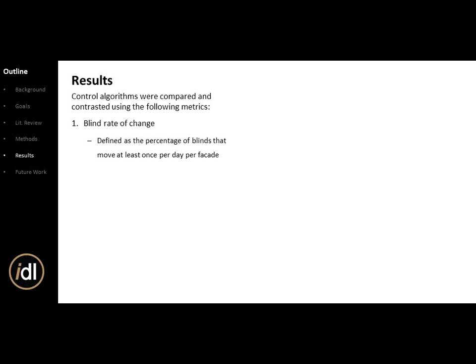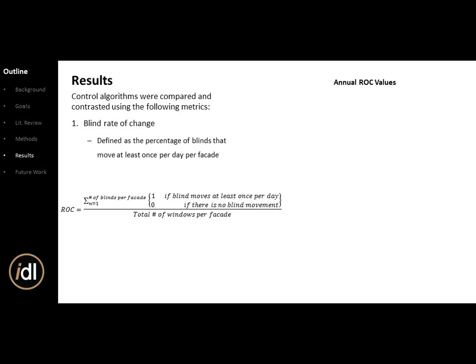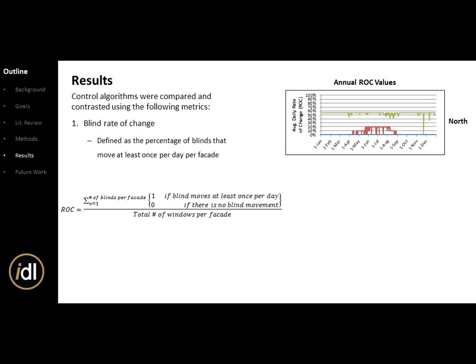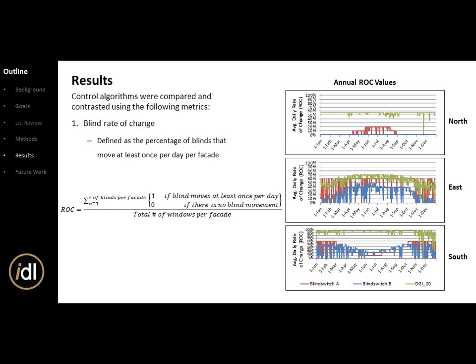The results I'll cover include blind rate of change, defined as the percentage of blinds that move at least once per day per facade. Annual rate of change values for north, east, and south facades show: red is Blind Switch A, blue is Blind Switch B, green is DGI 20. DGI has the highest rate of change because it's a simple above/below 20 trigger. Blind Switch A is close behind on the east facade, while Blind Switch B is lowest — and on the north facade, Blind Switch B never closes the window.